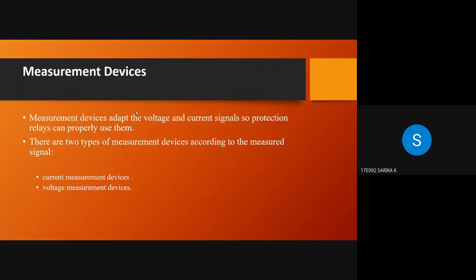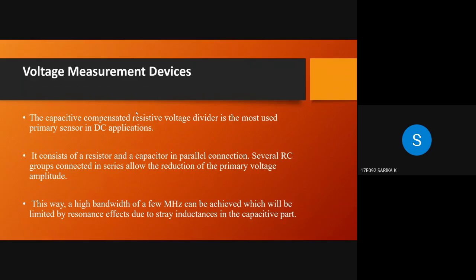First, let us see about measurement devices. Measurement devices adapt the voltage and current signals so protection relays can properly use them. There are two types of measurement devices according to the measured signal: current measurement devices and voltage measurement devices. In voltage measurement devices, the capacitive compensated resistive voltage divider is the most used primary sensor in DC applications. It consists of a resistor and a capacitor in parallel connection. Several RC groups connected in series allow the reduction of the primary voltage amplitude. This way, a high bandwidth of a few megahertz can be achieved, which will be limited by resonance effects due to stray inductances in the capacitive part.